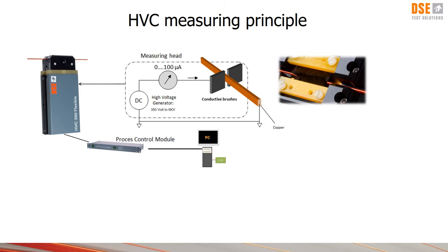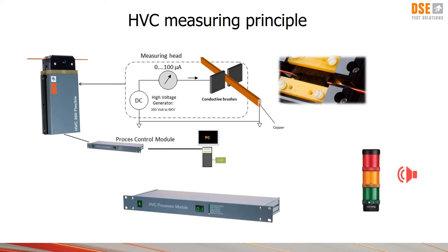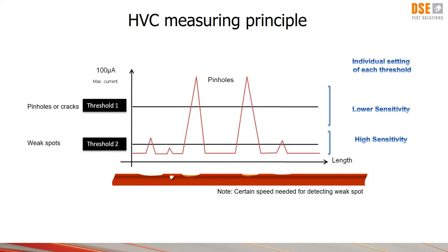The current being measured is sent to the connected processor module. When the error in the insulation is passing the measuring head the processor module is counting and gives an alarm in case the number of errors exceeds the limit being set in the software. This figure shows what happens with the current flowing in the brushes to ground. When the insulation is okay no current is flowing. At the moment an error such as a crack or pinhole appears, the current goes to its maximum.